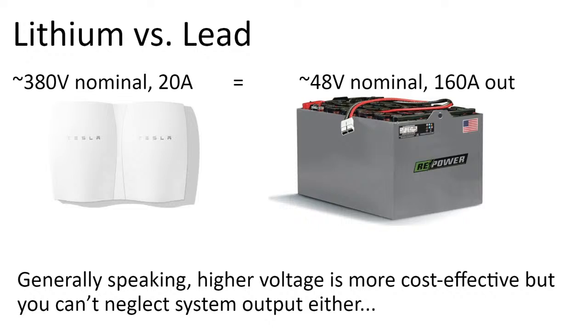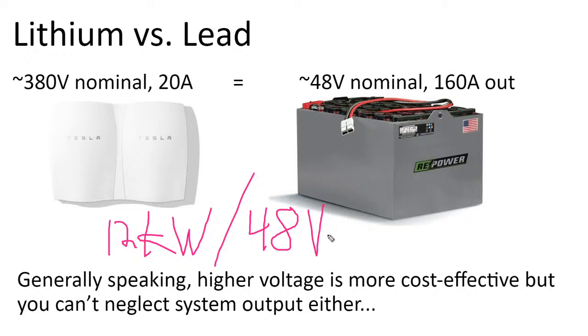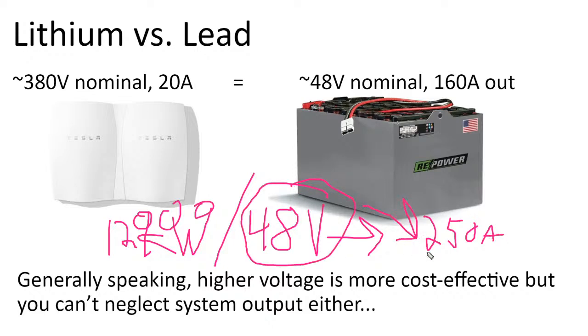The size of the inverter, the output capacity of the inverter, is going to throttle how much power can be dragged out of these things. There's no such thing as a free lunch. If you have a 12 kilowatt inverter and you're drawing it at 48 volts, that's 12,000 watts divided by 48 volts, so you're going to be drawing about 250 amps out of it. These low voltage systems on the DC side get to be very high amperage. So if you're ever looking at a battery with a very tiny wire out of it and you're trying to pull a very large load out of it, that's a safety issue.